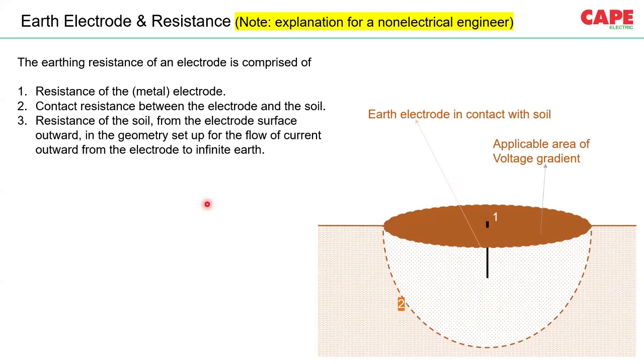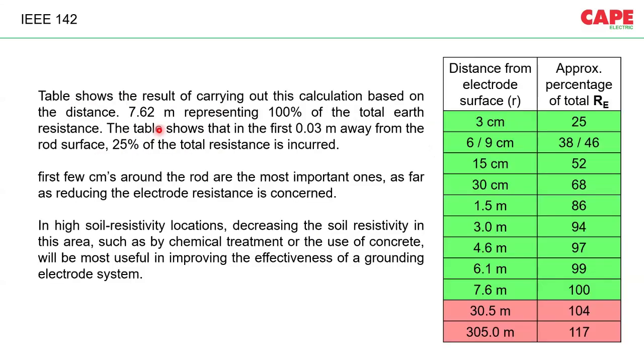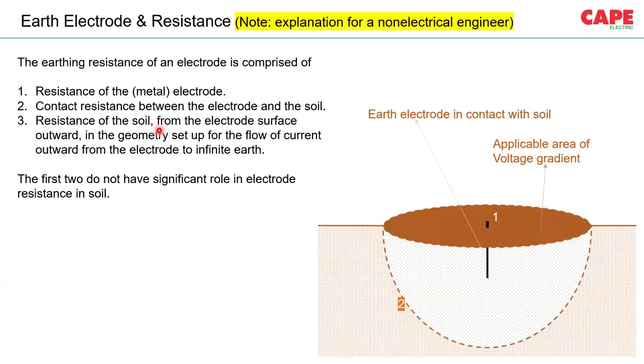Now, there are three factors which influence this particular electrode resistance. The first one is the resistance of the metal electrode itself. The second one is the joint, the contact resistance between the electrode and the mother soil. And the third one is the resistance of the soil itself. So the resistance of the soil is the most influencing factor. The first two are not much influencing, whereas the resistance of the soil is the most influencing factor in this particular case.